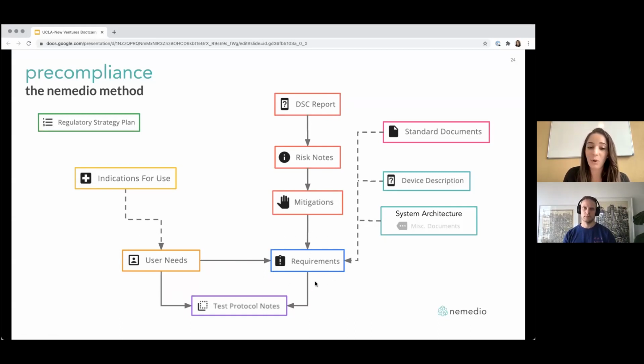It's to get you that full list of environments. So as we make our way through this diagram, the last thing here at the bottom is this concept of test protocol notes. The idea behind traceability is that you demonstrate that for everything your user needs to perform the use of your device, you have a requirement. For every way that we're making our device safe, we have a requirement. But we need to test that all of the requirements can be met by the product that you're building, and that when you build this product, your users are going to be satisfied and able to do the thing that you intend for your device to do. So there's this conceptual map between user needs, requirements, and then doing this thing called testing.